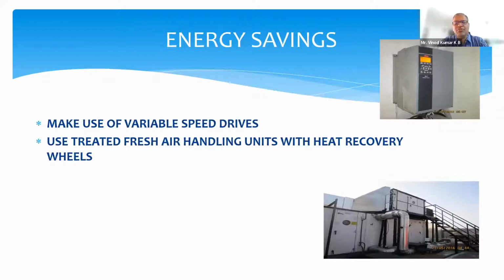Okay, and also the use of heat recovery, because since we are bringing fresh air into the building, we also need to throw the stale air out of the hospital. So there you need to use a heat recovery system. It takes the energy from the air which is going to be thrown out of the building and cools the fresh air coming into the building. It's basically recovering the temperature from the air that's going out of the building.